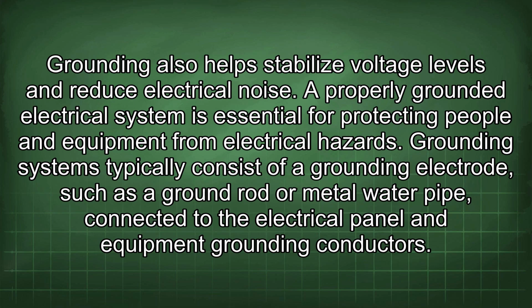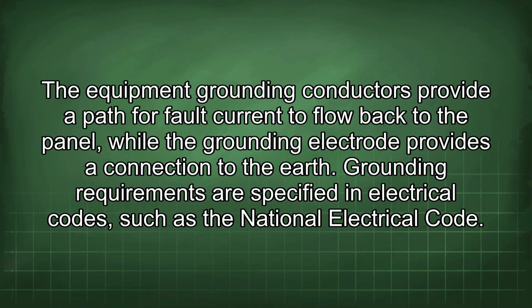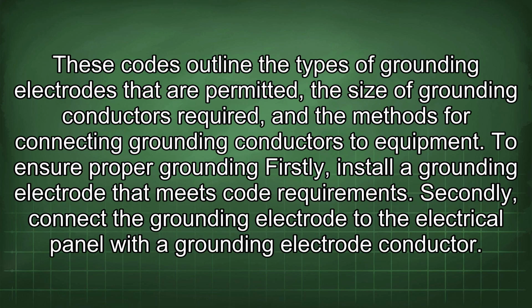Grounding systems typically consist of a grounding electrode, such as a ground rod or metal water pipe, connected to the electrical panel and equipment grounding conductors. The equipment grounding conductors provide a path for fault current to flow back to the panel, while the grounding electrode provides a connection to the earth. Grounding requirements are specified in electrical codes, such as the National Electrical Code. These codes outline the types of grounding electrodes that are permitted, the size of grounding conductors required, and the methods for connecting grounding conductors to equipment.